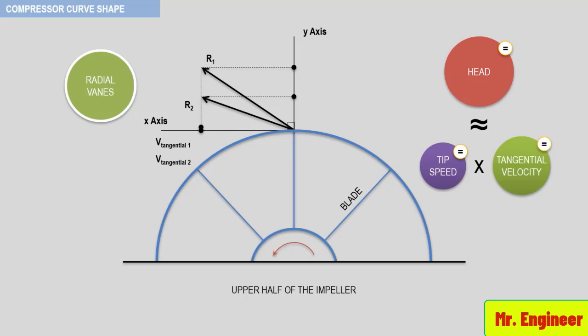Therefore, the curve shape will be flatter and will possess much less of a head rise than that of a non-radial vane. In reality, the effects of friction will produce a curve shape that increases from high flows to low flows, but with much less of a head increase — typically around 3% head rise or less. This is an important fact, since the operating point of any centrifugal compressor is the intersection of the head required by the process and the head produced by the compressor. A compressor with a low head rise curve will be extremely sensitive to process changes compared to one with a higher head rise.